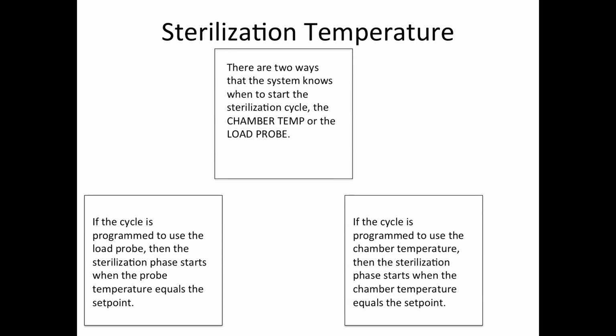There are two ways that the system knows when to start the sterilization cycle: the chamber temperature or the load probe. Let's look at the load probe. This is that thermocouple on the end of the green cable. So if the cycle is programmed to use the load probe, the sterilization starts when the probe temperature equals the sterilization set point.